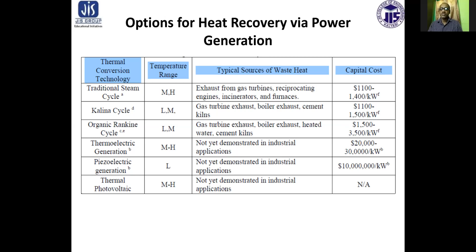Now the very popular one: generating power via mechanical work. First of all, mechanical work can be generated from waste heat through the steam Rankine cycle. The most frequently used system for power generation from waste heat involves using the heat to generate steam, which then drives a steam turbine. A schematic cycle is shown in the next slide. The traditional steam Rankine cycle is the most efficient option for waste heat recovery from exhaust streams with temperature above about 340 to 370 degrees centigrade.